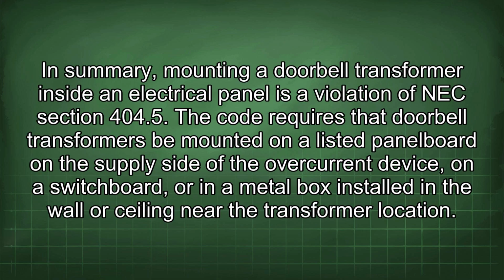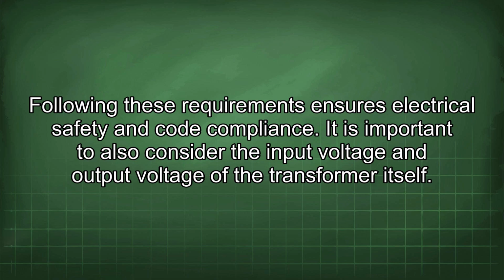In summary, mounting a doorbell transformer inside an electrical panel is a violation of NEC Section 404.5. The code requires that doorbell transformers be mounted on a listed panel board on the supply side of the overcurrent device, on a switchboard, or in a metal box installed in the wall or ceiling near the transformer location. Following these requirements ensures electrical safety and code compliance.